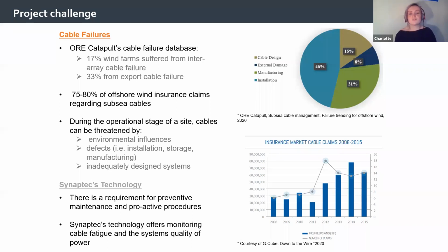During the operational stage of a site, cables can be threatened by environmental influences, misdesigned systems, or defects occurring in the cable before operation. The cable can be affected by environmental influences such as changes in the water movement resulting in scour or seabed movement. The cable moving can cause damage over time.